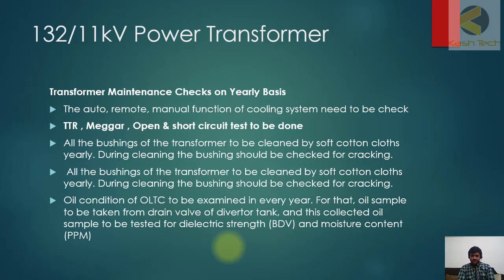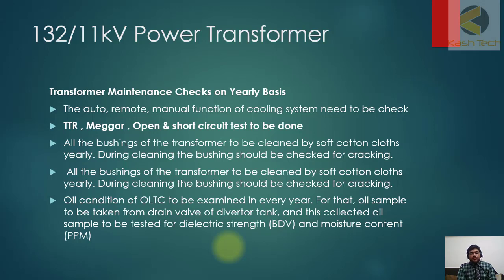On a yearly basis: the TTR (Transformer Turns Ratio) test, megger test, open circuit and short circuit tests should be done. All bushings of the transformer should be cleaned using soft cotton clothes, and during cleaning the bushings should be checked for cracking.